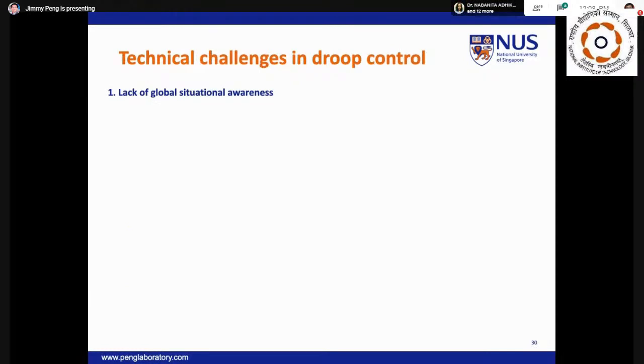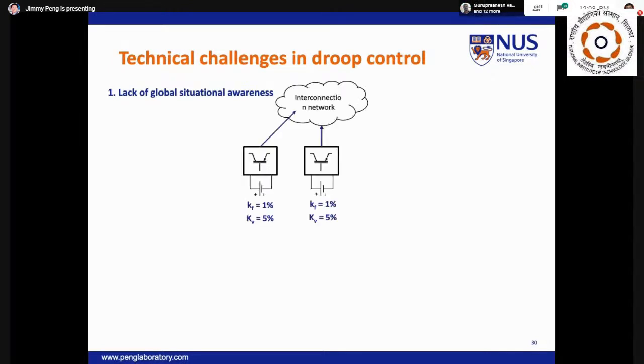Now, Droop control design is not a straightforward job in practice due to the lack of global situational awareness among the individual inverters. The stability problem actually becomes more complex in the presence of multiple grid-forming inverters. Now, suppose we have 2 inverters, and we would like to add a third one to the network. The selection of the Droop gains is a tricky task.